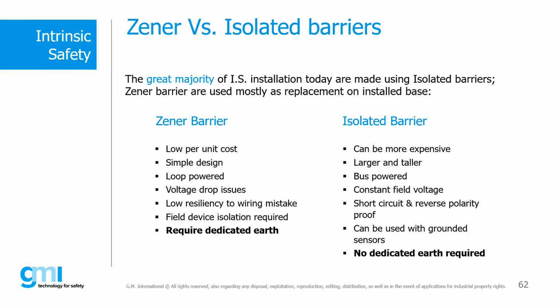So the earth connection is very important for each Zener barrier you're using, and it must also be checked frequently. While an isolated barrier is of course more expensive because the circuit is more complicated and bigger, it can be used with any sensor, with any field device, and doesn't require any earth connection.